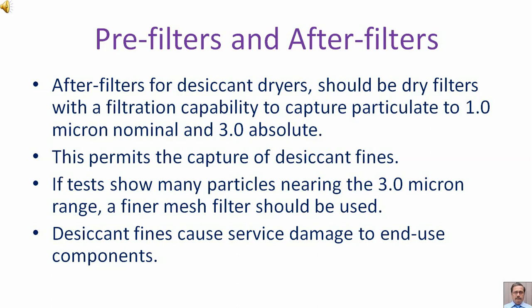After-filters for desiccant dryers should be dry filters with a filtration capability to capture particulate to 1 micron nominal and 3 micron absolute. This permits the capture of desiccant fines. If tests show many particles nearing the 3 micron range, a finer mesh filter should be used.